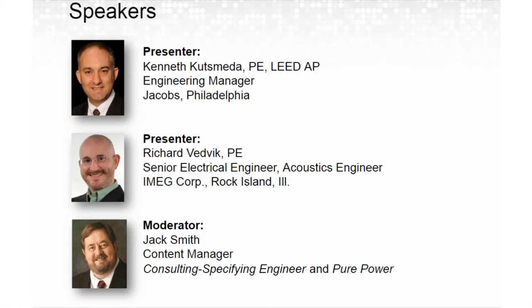With the increased efficiency requirements for transformers, are they less robust, in other words, more susceptible to failure? When we look at all of the losses that I described within the transformers, and how those originate, whether they're load losses or core losses, we can think about how a transformer is constructed and how that relates. Load losses are losses that vary and increase as load increases, and those are usually helped by making things bigger, i.e. they become more robust. We use larger wire, we use copper instead of aluminum. So we can reduce those load losses by making transformers more robust.